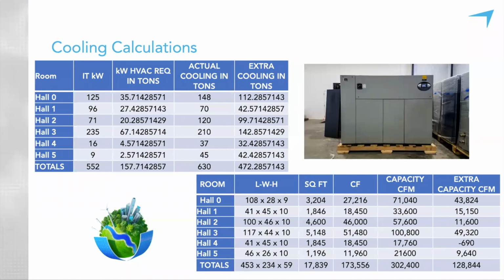We always, in data centers, plan for failure. We have redundancy in N+1, 2, 3, and 4 in almost every fashion that you can imagine. So newer technologies, being able to do what I call team crack units, where we connect the CRAC units through a standard network switch where they all talk together and work as one, now we can look at N+1 a little bit differently. And I cannot tell you what is right and what is best. Every data center has to make their own decision on this.